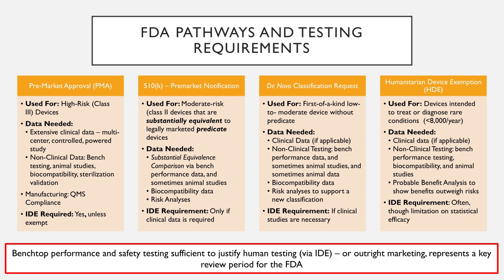Now, in order to do whatever limited subset of that clinical study that you would have to do, you would still need that IDE. So one of the main points that I'm trying to get across here is that for all four of these pathways, the IDE process or collection of benchtop testing, biocompatibility testing, and whatnot represent a significant milestone in going about these pathways.